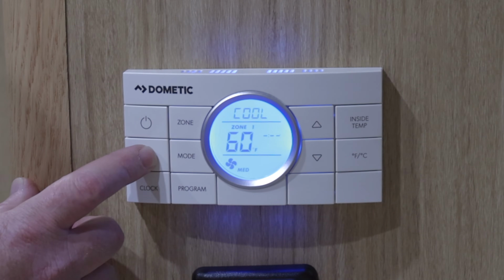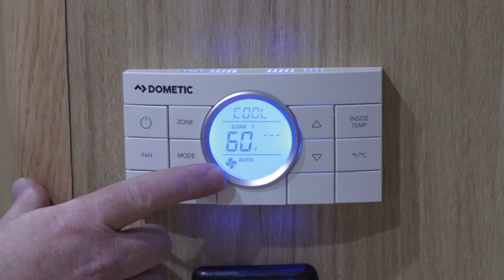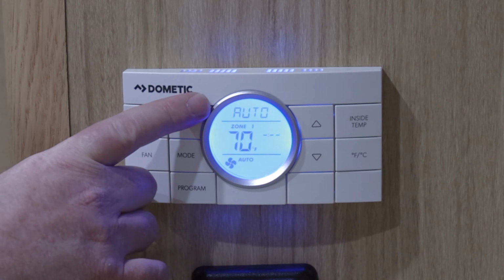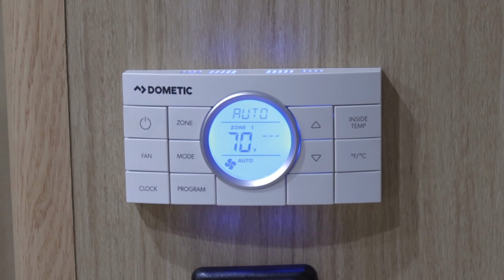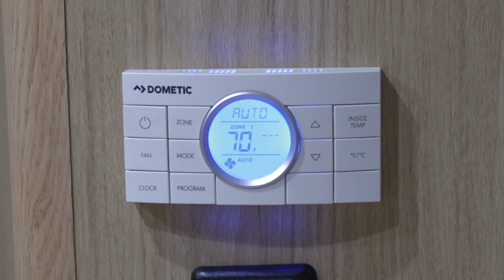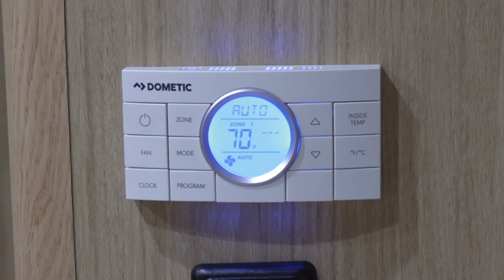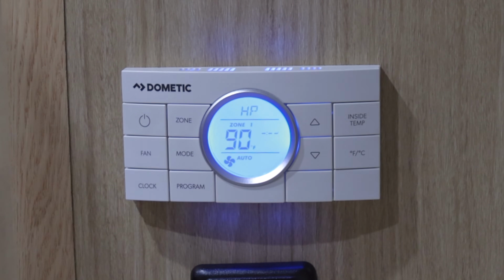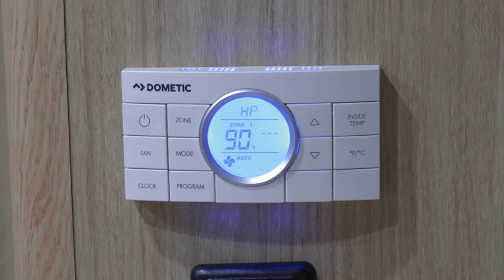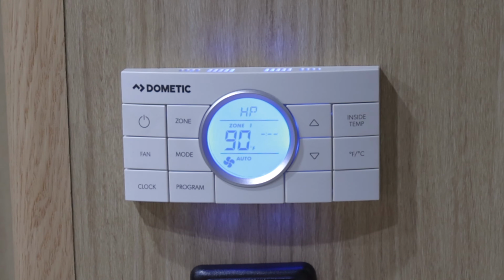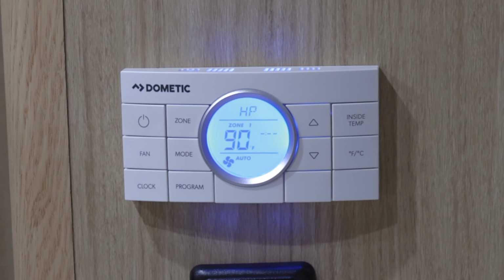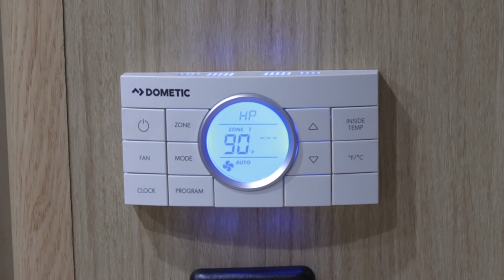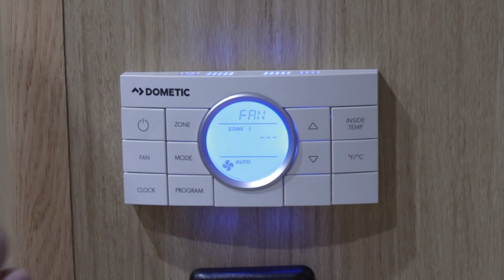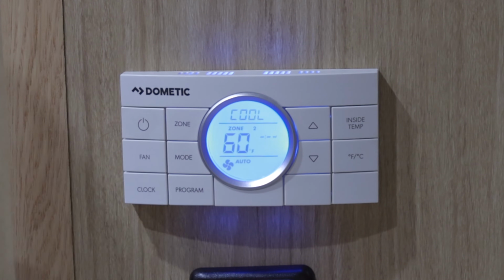So we'll cycle through to where it says auto, and then with the mode button, we've got an auto across the top. The auto across the top is going to automatically switch between the air conditioner and the heat pump control. The heat pump is your next option. It makes a little whooshy sound as it switches over, so we're going to listen for that. Now, remember, your heat pump is electrical, so you've got to be plugged into your shore service for it to work. On Zone 1, after the heat pump, we're going to find a fan-only option, and then we'll have it off. We'll switch to Zone 2, and we'll be able to fire that one up.